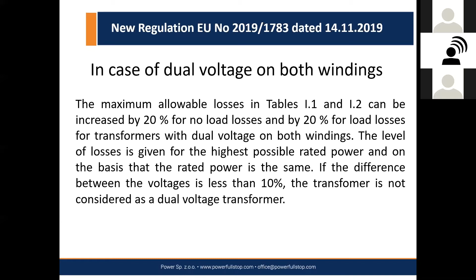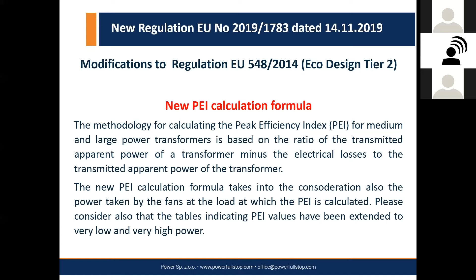What is maybe the most important point of this new modification is the new peak efficiency index formula. What happened is the first formula was not considering the fact that there is also a part of power used by the fans during operation of the transformer. So if you look at this new formula, you'll find this new point, PC0, referring to the electrical power required by the cooling system for no-load operation. So the new formula has been extended in that case.